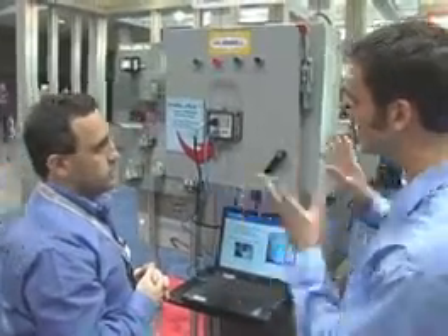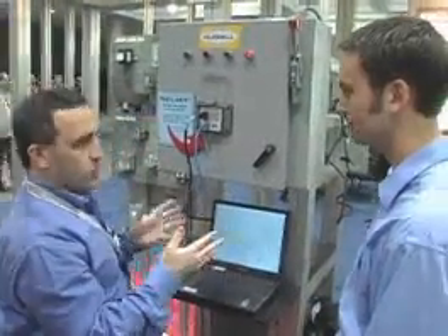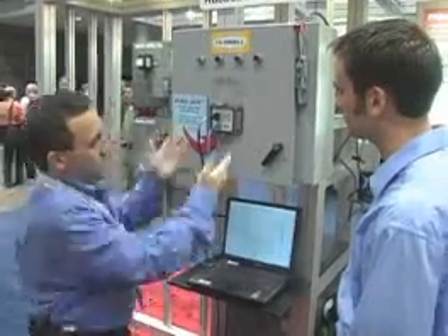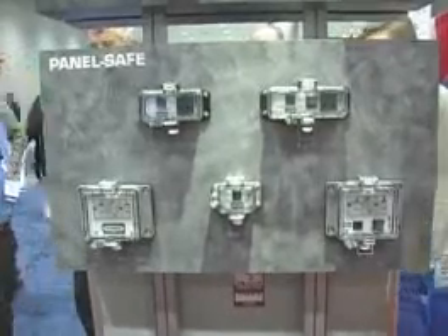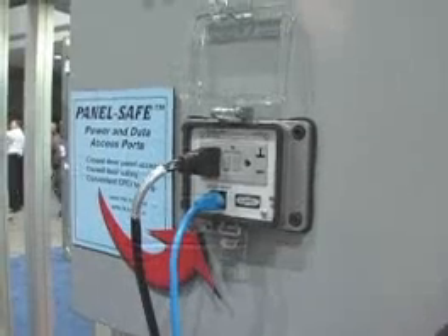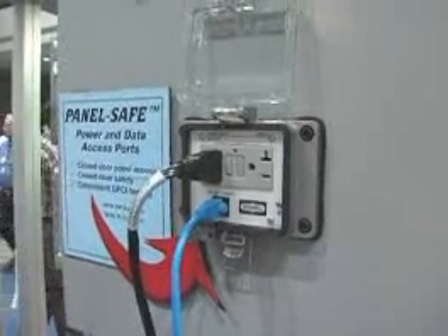So tell me, Roy, how does this device separate itself from the others? What's special about it? There are a couple of important features of this product that separate it from others that might be on the marketplace. Firstly, we use a ground fault receptacle. There is a new code requirement that insists that any utility receptacle used in a control cabinet application be ground fault protected. Hubbell PanelSafe has ground fault functionality in it.